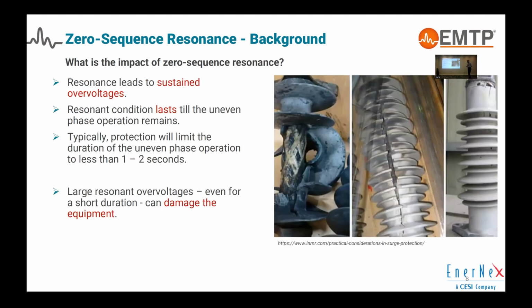Well, if there is a zero sequence resonance, is it an issue? Yes, because it leads to high overvoltage, and even for short duration, it can damage the equipment. And it would remain energized until there is an intentional action to remove that unbalance or resonance operation.